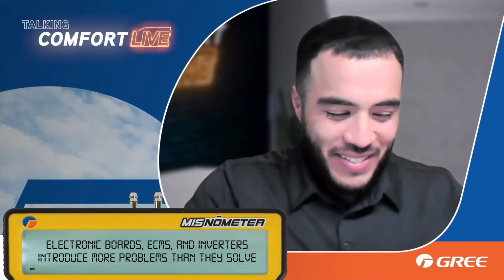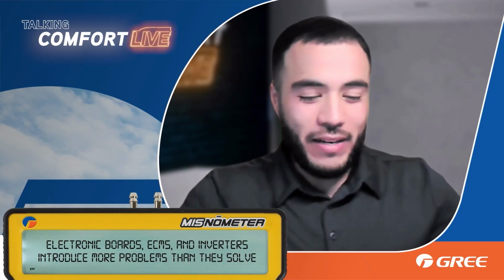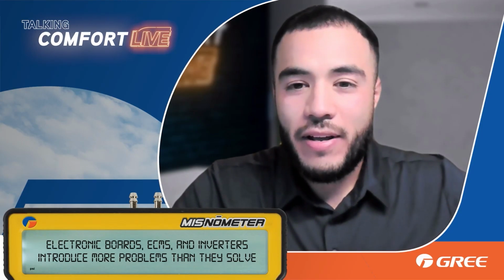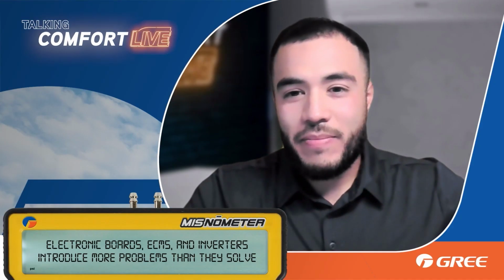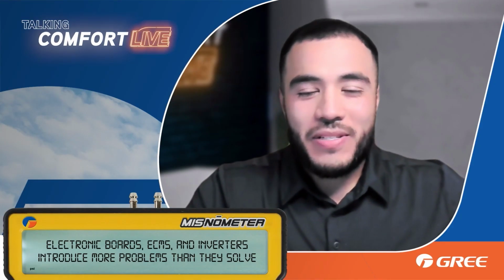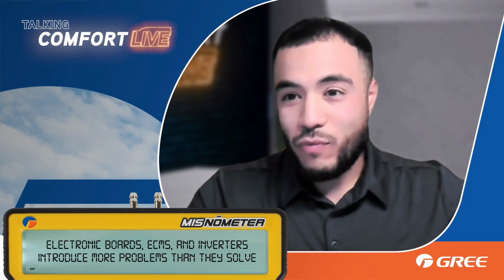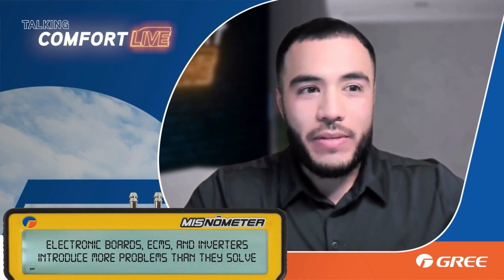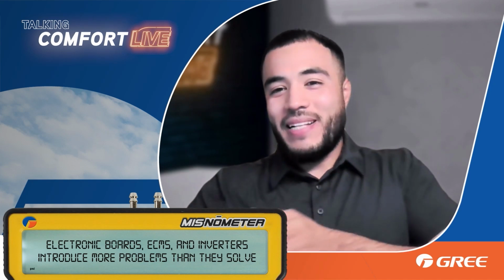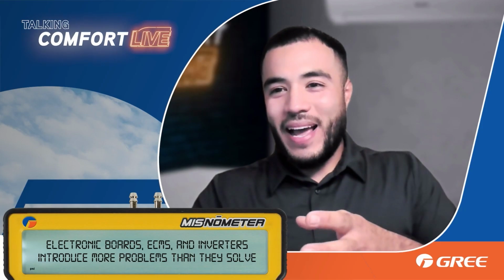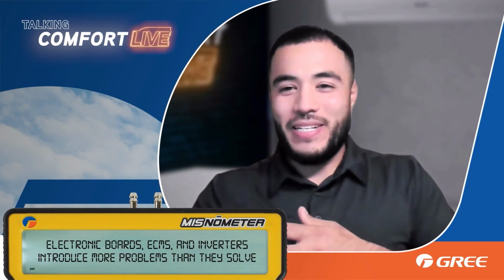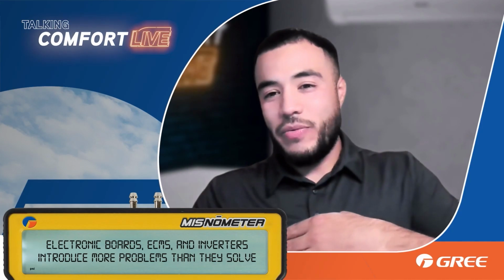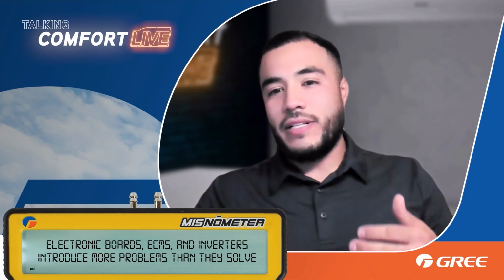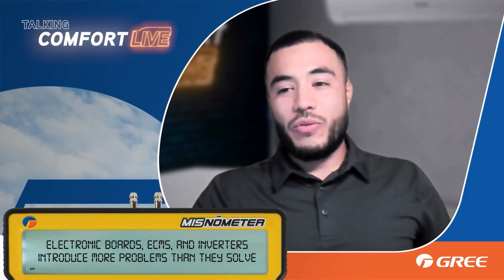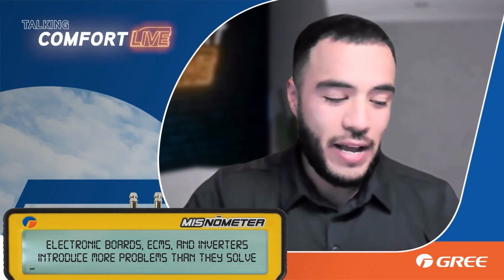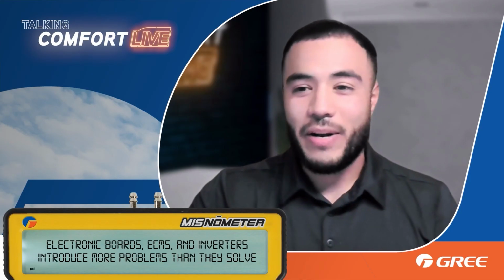Okay, all right. I just want to piggyback a little on what Greg was talking about, the inrush current for the motors, PSC versus ECM. With ECM, it slowly ramps itself up until it gets to its full speed, its full output, whatever the program is in the ECM. Now we compare that to the PSC, where we get pretty much a jolt to get it going to 100%. It doesn't do that gradual ramp, and that's where you don't get the efficiency that you get out of the ECM motor. Those are really good points Greg pointed out, and I just wanted to address that. The inrush is definitely a lot lower when we're talking about ECMs.